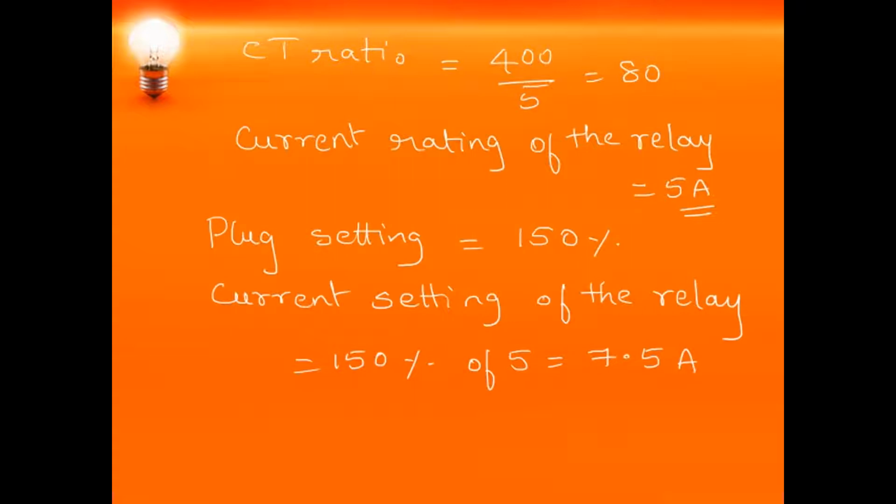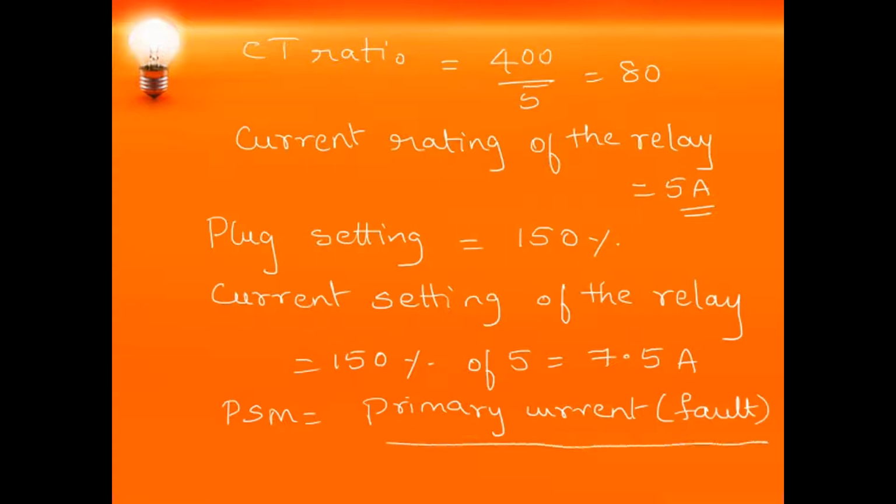Okay. So now we will find PSM. PSM is nothing but primary current, which is the fault current, divided by relay current setting into CT ratio.